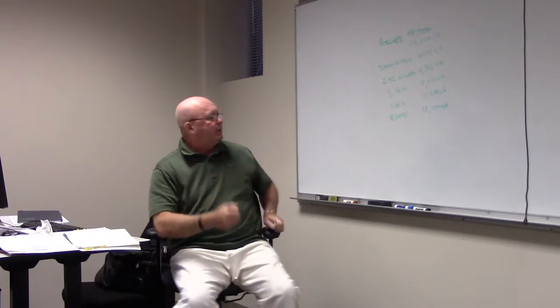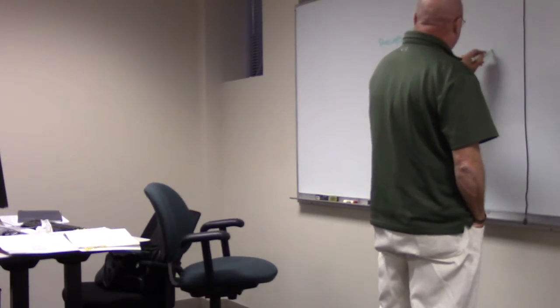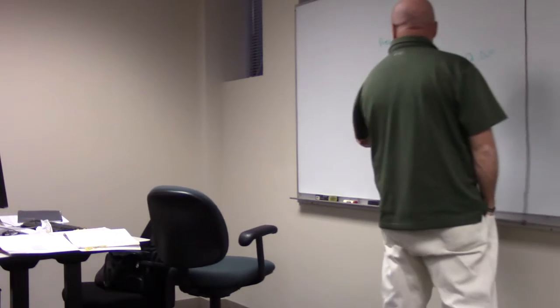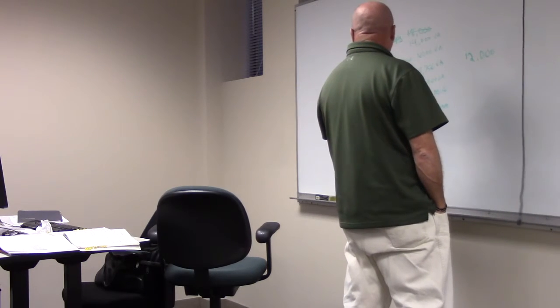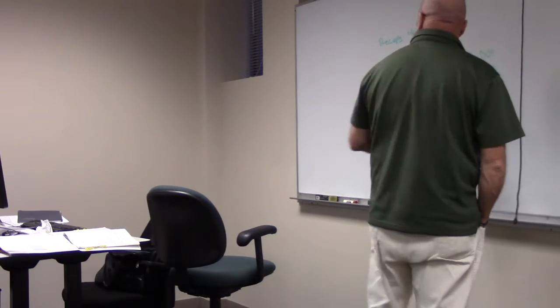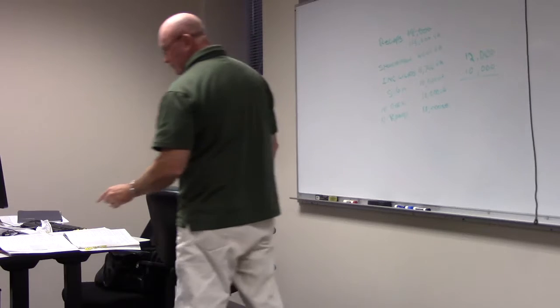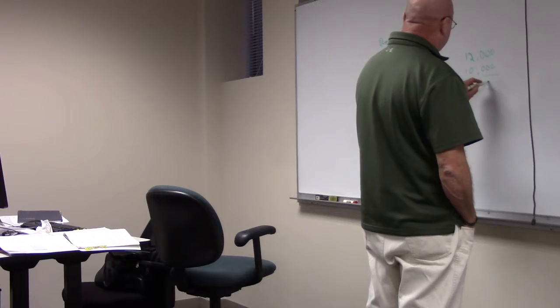So step number 8, we're breaking out the continuous and non-continuous. It tells us, and I agree, the non-continuous would be a range. It's probably not going to be put on for 3 hours, is it? What's the other one that told us it was non-continuous? An oven? Yes. Didn't it tell us that the only two they list is non-continuous? Yeah. So our non-continuous load is 22,000. That's non-continuous. Just don't put NC.